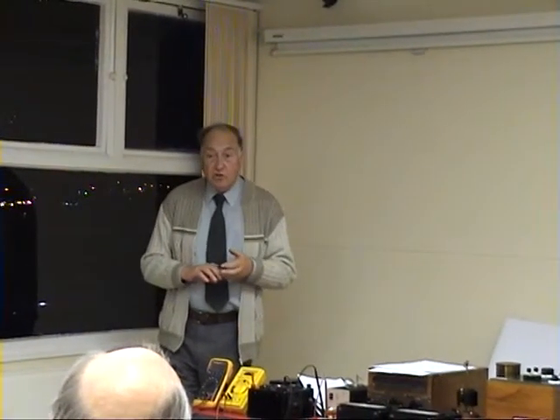Now, this is the horror story. This is for real too, and why I can always recommend Fluke. When I was at Emerson, we had on trial some Philips meters, and these were the handheld meters. Nice meters, but they had a feature on them which ruled them out forever from Emerson after that, is that the 10 amp range on it was a straight piece of metal inside. There was some sort of current shunt inside.